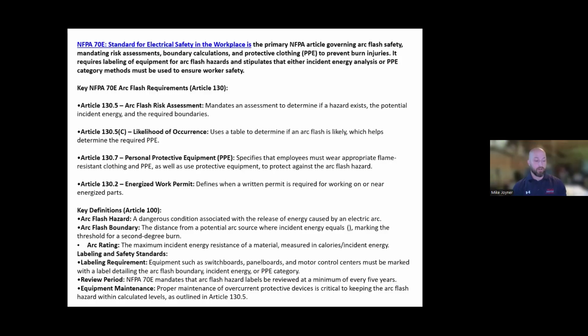There were a couple instances I worked on, a couple buildings in Boston, where they had a utility guy wearing a 40 cal suit. It wasn't properly calculated — the actual cal rating needed was way beyond that. There was a fault. He was wearing his proper PPE, but it wasn't calculated right, and once that fault happened, the flash was so great it burnt the suit right off his body. He came out not wearing the suit anymore.